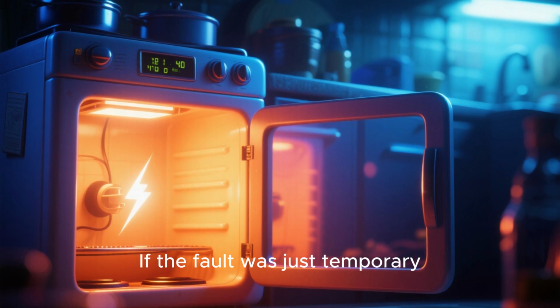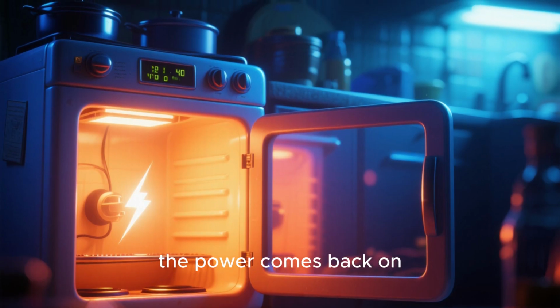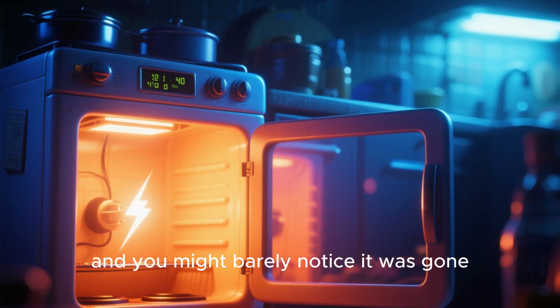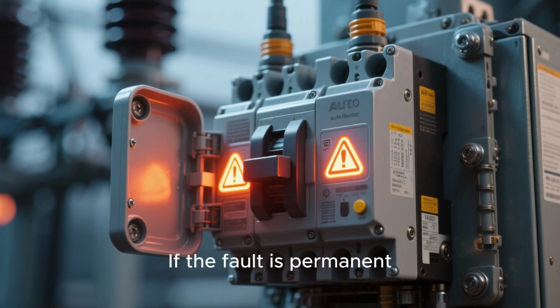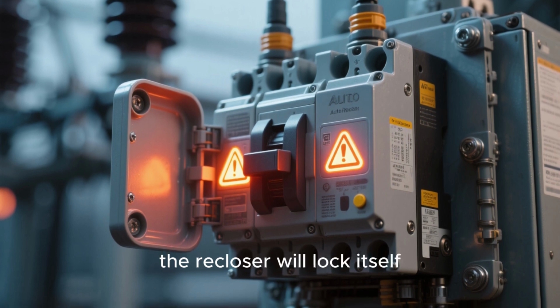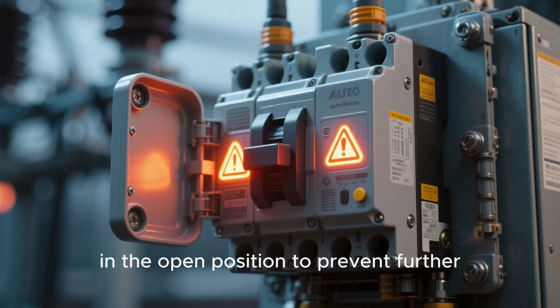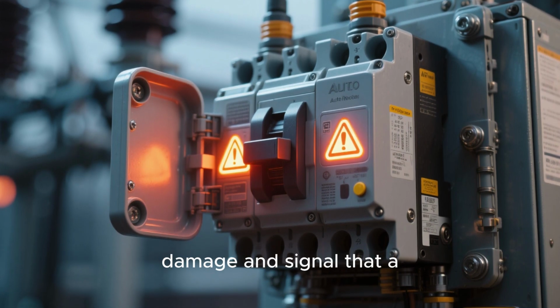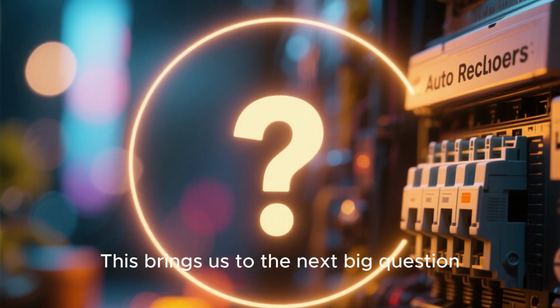If the fault was just temporary, the power comes back on, and you might barely notice it was gone. If the fault is permanent, the recloser will lock itself in the open position to prevent further damage and signal that a repair crew is needed. This brings us to the next big question. Why are these devices so essential?